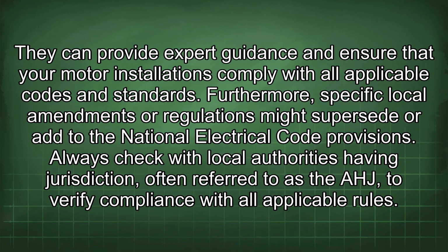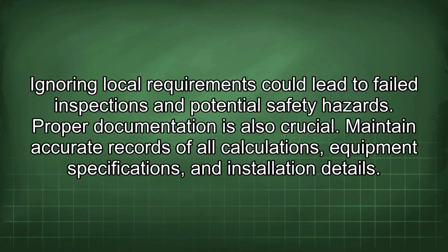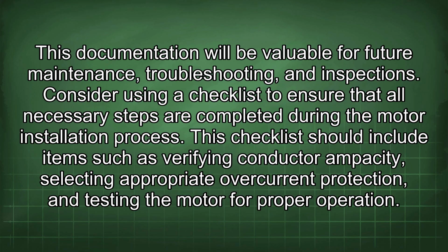Furthermore, specific local amendments or regulations might supersede or add to the National Electrical Code provisions. Always check with local authorities having jurisdiction, often referred to as the AHJ, to verify compliance with all applicable rules. Ignoring local requirements could lead to failed inspections and potential safety hazards. Proper documentation is also crucial. Maintain accurate records of all calculations, equipment specifications, and installation details. This documentation will be valuable for future maintenance, troubleshooting, and inspections.